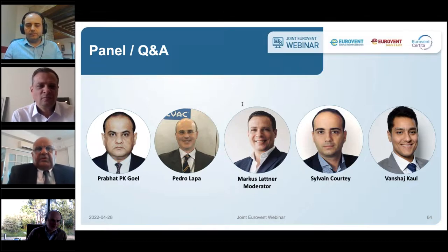Just dehumidifying on the cooling coil is not the best way to bring down the humidity. Cooling coils are there to dehumidify your air, but you must use something which takes out the moisture from the air before it goes to the cooling coil. And if it is a dry warehouse, it takes time to dry it. I'm sure the warehouse will require fresh air. It's not a warehouse which can do without fresh air. If it can, it's a different story altogether.